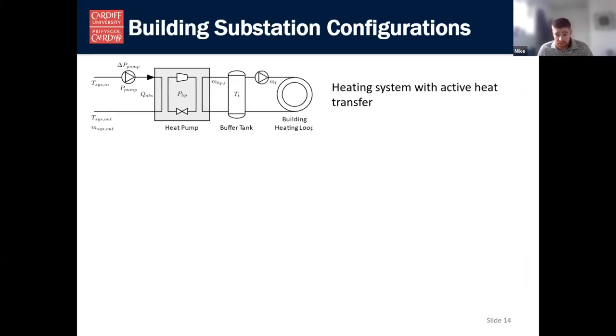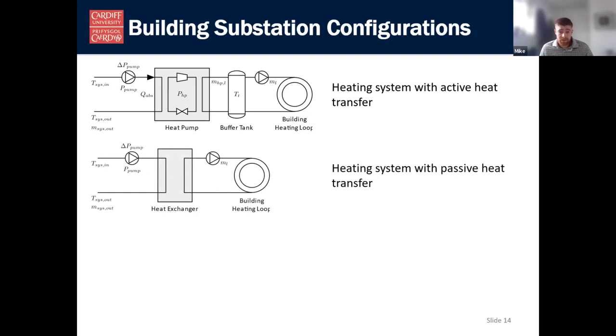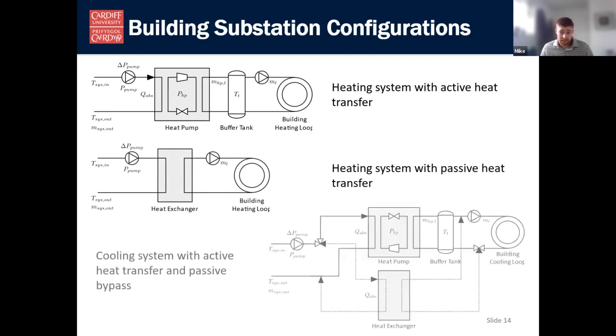Similarly, for building substations, in the case of heating, if the nominal pipe temperature is lower than the supply temperature of the building, we need a heat pump. But if it's high enough, we can just use a heat exchanger for passive heat transfer. And for variable nominal pipe temperatures, it may be possible to passively cool buildings when temperatures allow. But we may need to retain the option of an active cooling as ground temperatures can change throughout the year. And the heating and cooling systems of the building substations will be modelled with one of these 3 configurations.